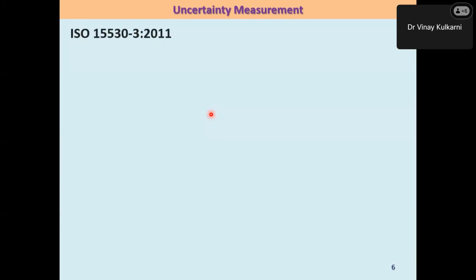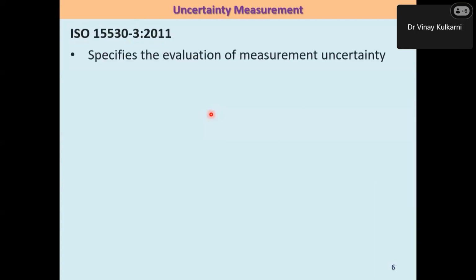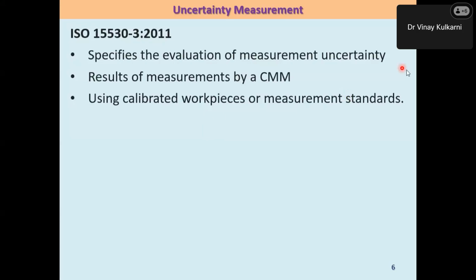So let us see the journey of ISO in CMM. ISO 15530-3 in 2011 specifies the evaluation of measurement uncertainty by CMM using a calibrated workpiece or a measurement standard. This is very important here. Why is a calibrated workpiece required? Because its dimensions are known and we are comparing whether the CMM is going to give the same dimension or not. Now, let's say, for example, we have checked the roundness by using Taylor Hobson, a more sophisticated measuring device. And then we check the same in the same condition, whether the CMM also gives the same result or not. That is traceability standard. By defining the experimental technique, this is what they have defined in ISO 15530.